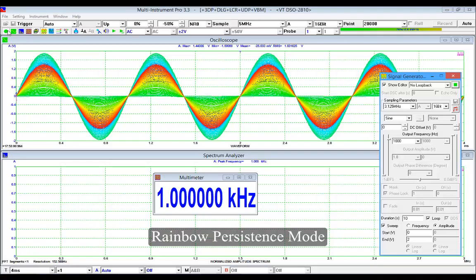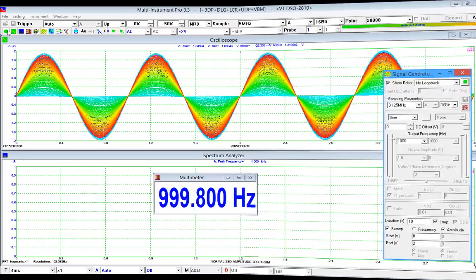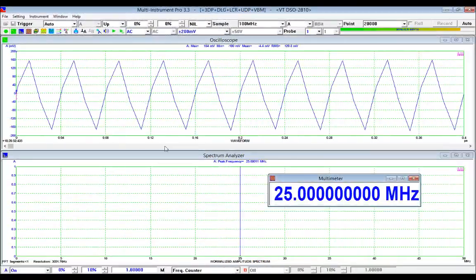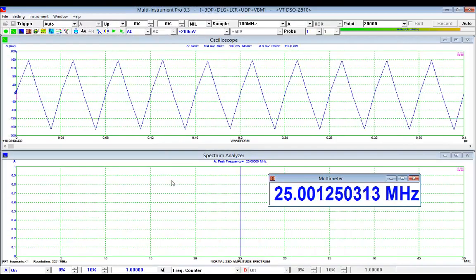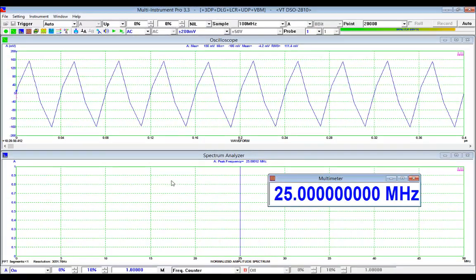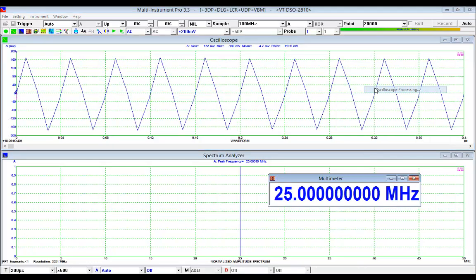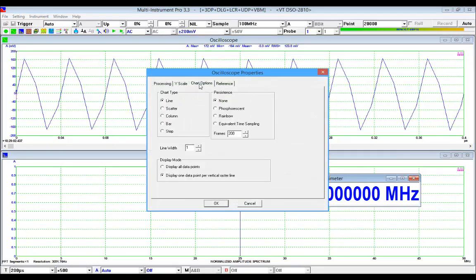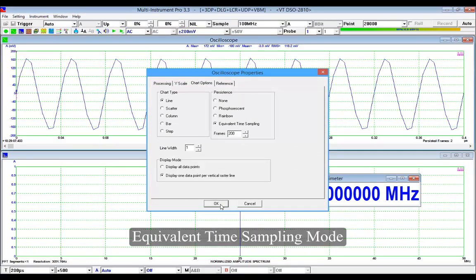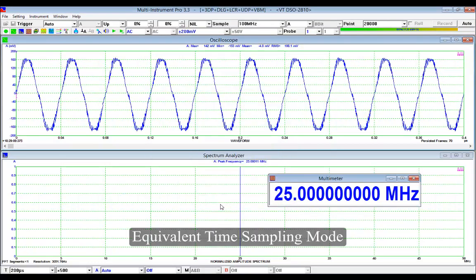Now we demonstrate the equivalent time sampling function. The input signal is a sine wave at 25 MHz. The sampling rate of the oscilloscope is 100 MHz, therefore only 4 samples per cycle. Now we change it to equivalent time sampling mode. As you can see, the waveform looks better.